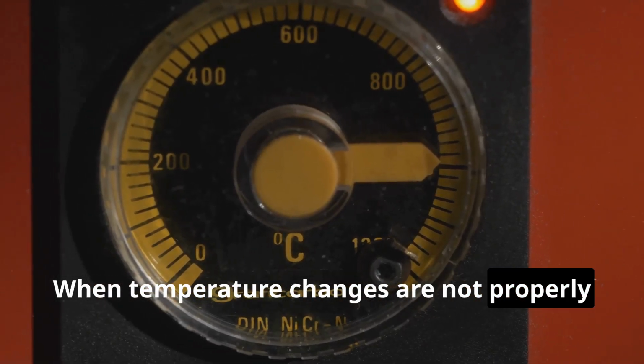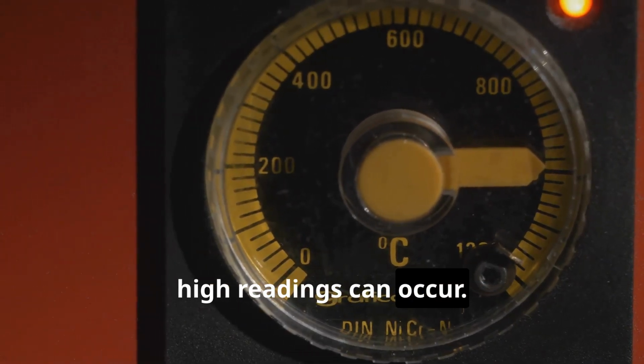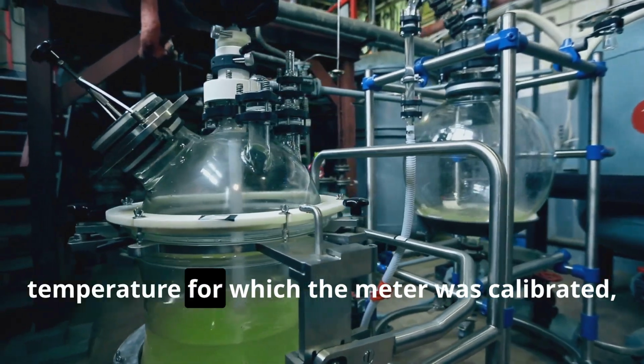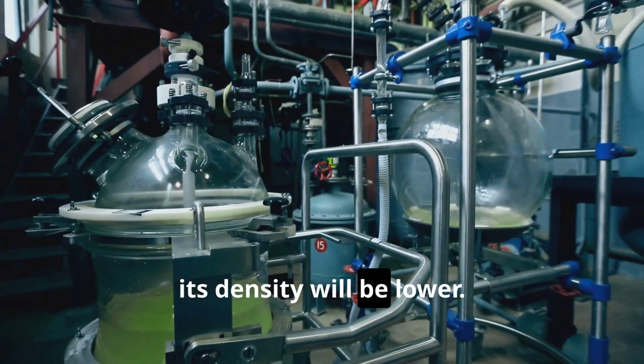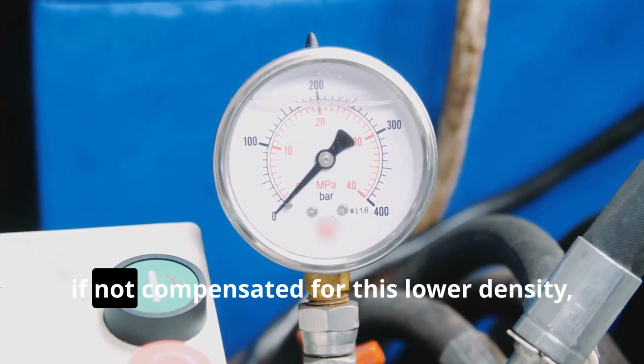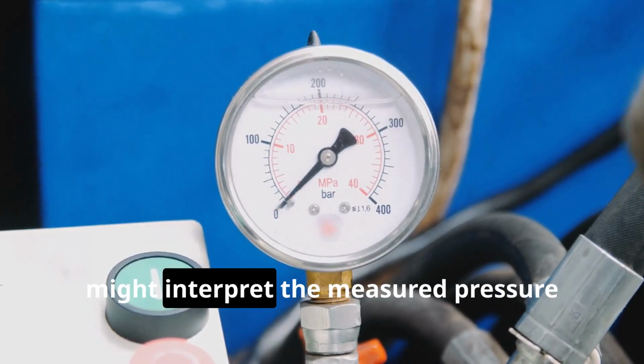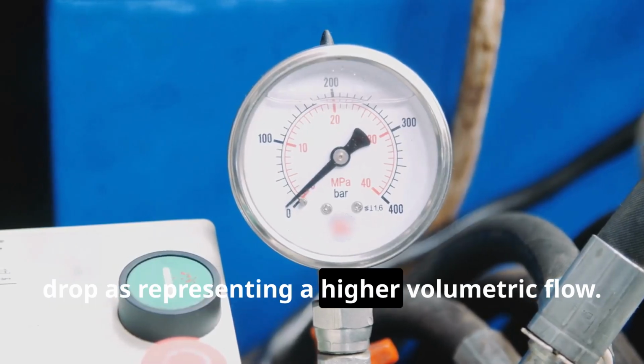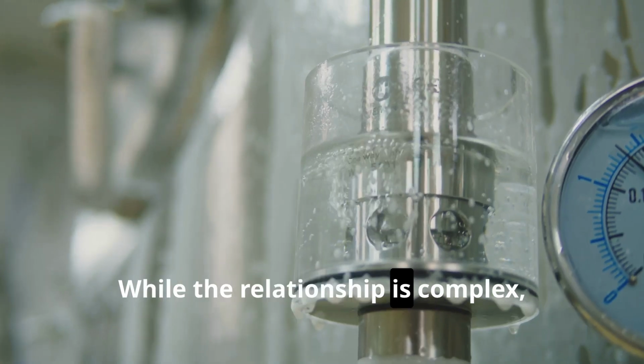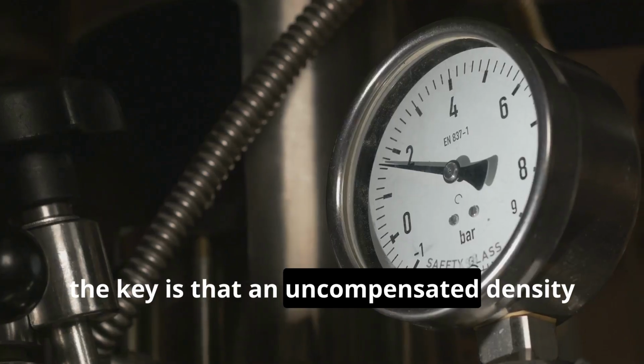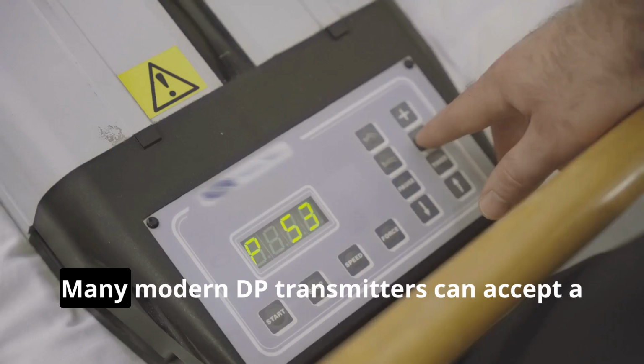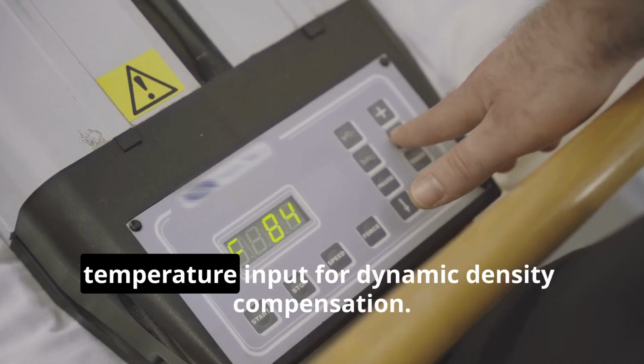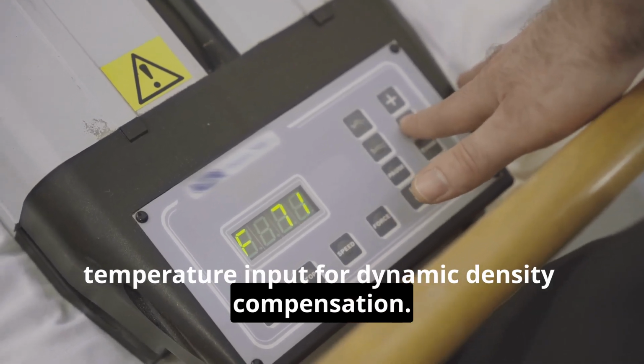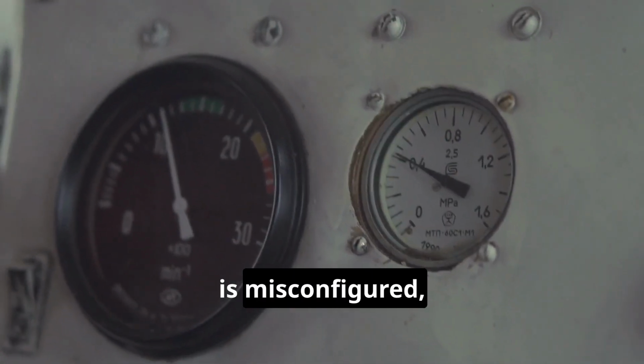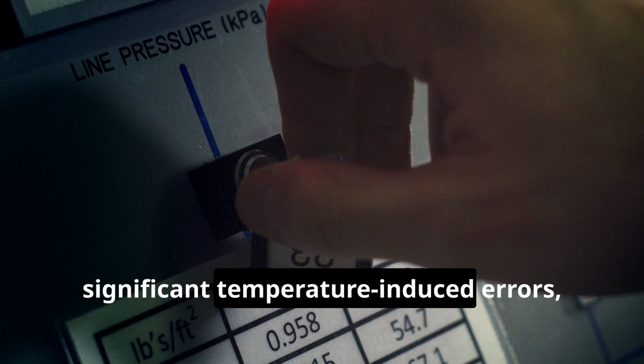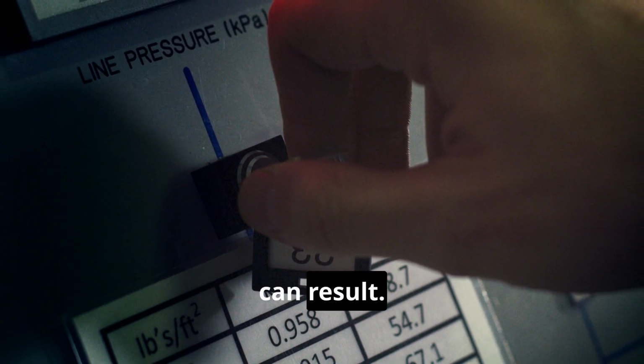When temperature changes are not properly accounted for, high readings can occur. For example, if a liquid is hotter than the temperature for which the meter was calibrated, its density will be lower. The DP flow calculation, if not compensated for this lower density, might interpret the measured pressure drop as representing a higher volumetric flow. While the relationship is complex, the key is that an uncompensated density change leads to error. Many modern DP transmitters can accept a temperature input for dynamic density compensation. If this compensation system fails, is misconfigured, or is not present, significant temperature-induced errors, including high readings, can result.